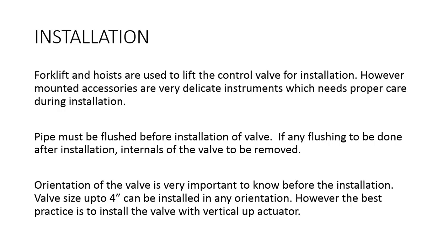In one case, the flushing was done with a specific chemical which reacted with the o-ring of the valve, due to which the valve was leaking after installation. Hence, one must be aware of such chemical compatibility. It is better to speak to the valve manufacturer in case such a special chemical is used for flushing purpose.